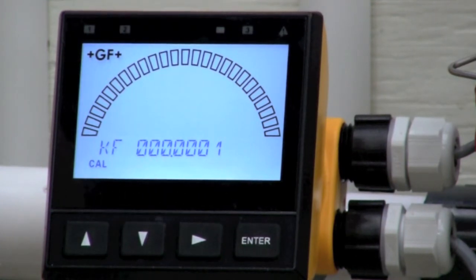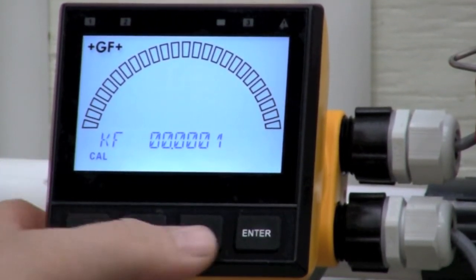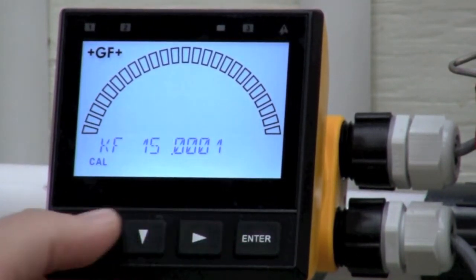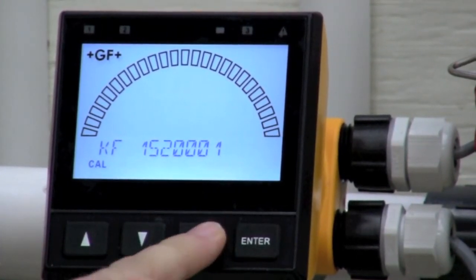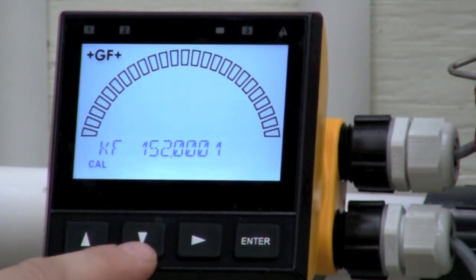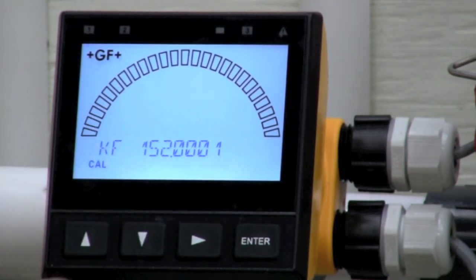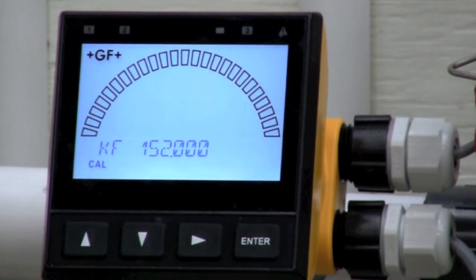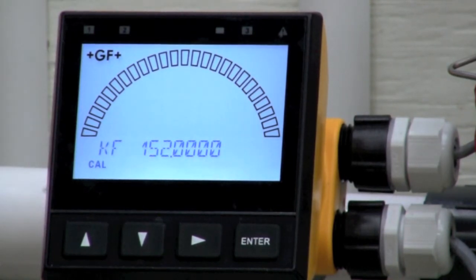The K-factor I'm looking for is 152. I'm going to use the up and down arrows to get me 1, 5, 2. If you overshoot, just hit the down arrow. When you're doing this, take note of your decimal. Right now, I have the decimal selected. I can move this decimal to anywhere I want. This is indeed the correct spot. Now that I have my K-factor entered in, I hit enter. It tells me saving. There we go. We have the K-factor set in.